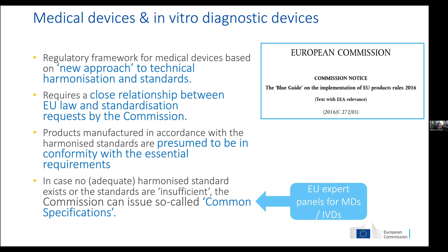So very briefly to sum that up, conformity assessment is against harmonized standards in Europe. That means that if the notified body or the manufacturer look at the harmonized standards to confirm the conformity of the device with the standards, then you have directly a conformity with the essential requirements of the legislation.